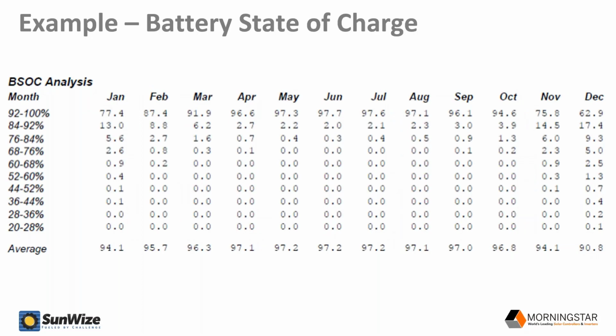All right, looking at this is what's called a battery waterfall chart, and it shows the estimated percent of time that the battery will spend in each given state of charge bracket for a given month. So what ruins batteries, going back to this poll question that we had about how long your batteries last, what ruins lead acid batteries is remaining in low states of charge for prolonged periods of time. So a 20% state of charge or an 80% depth of discharge is the typical cutoff LVD, which is why this chart ends at the 20 to 28%. Therefore, any time spent below that would be considered a low voltage disconnect or a load failure.